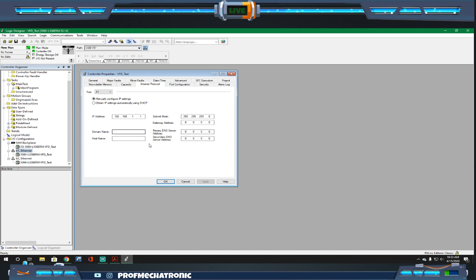Now from here we can add a new module and look for the PowerFlex 525. If I look back here, you'll see there's a huge list of stuff in here. Some of them are grayed out, some are not, because some of these can be added online and others cannot. In this case we're looking for a PowerFlex 525, so I just use the keyword 525, and it brings up the 4 that we have available to us.